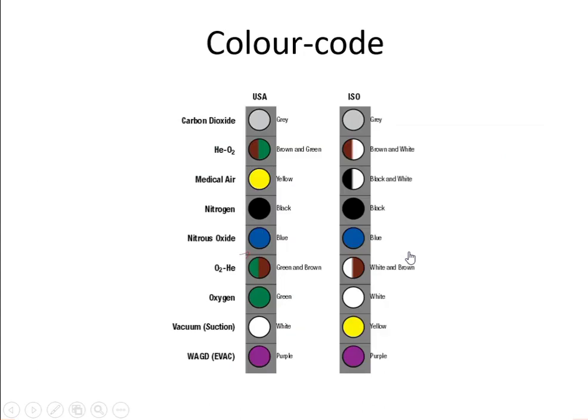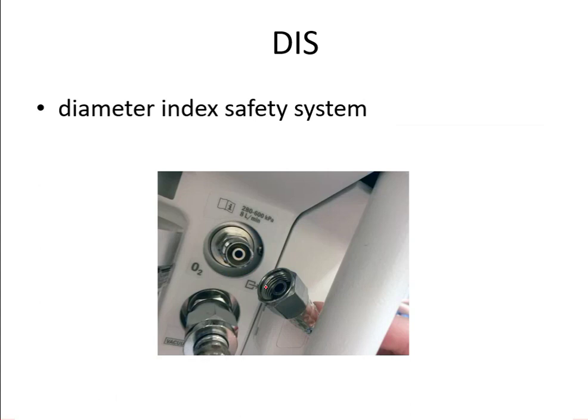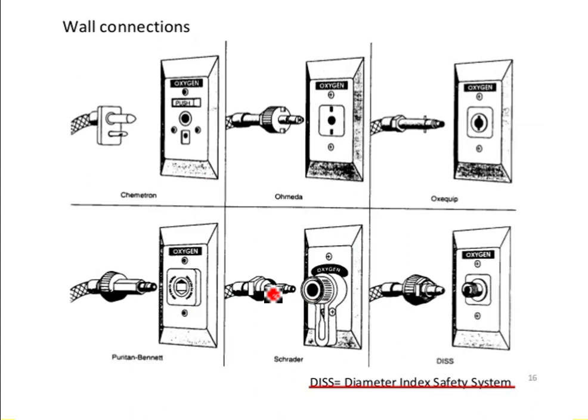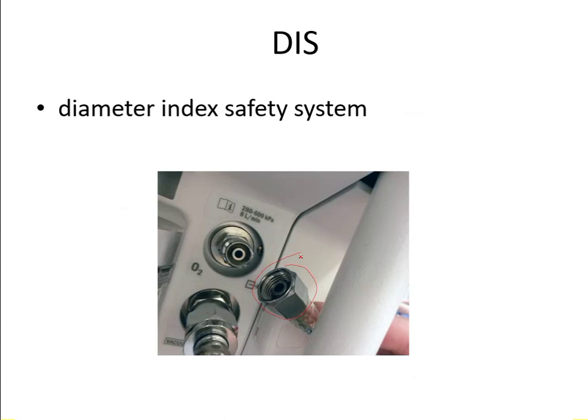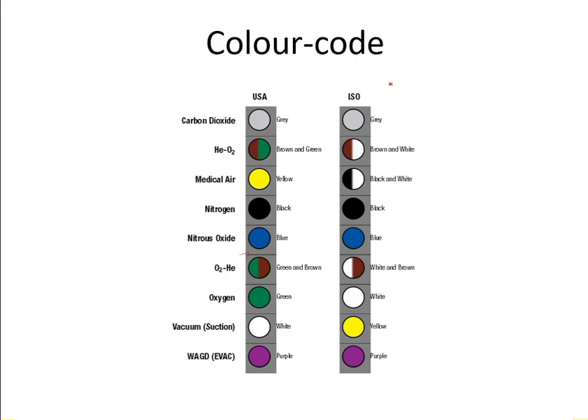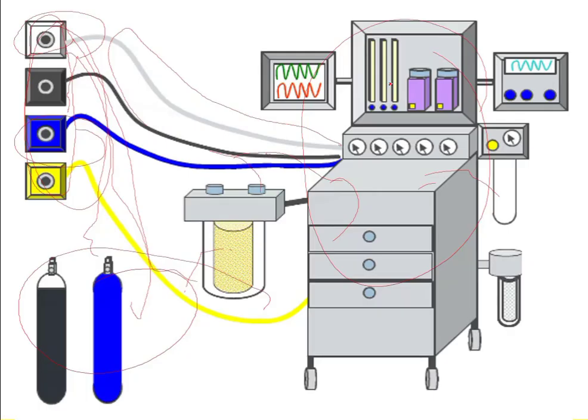This is the color code system. The other safety system is the diameter index system. Each pipeline can only connect to its wall connector with a specific diameter that is different from one gas to another. For example, the oxygen connection diameter is different from the air connection diameter. The color code and the diameter index system together prevent the disastrous complication of supplying the wrong gas to the patient. The pipelines deliver gas from the wall of the operation room into the anesthesia machine through both these safety systems.